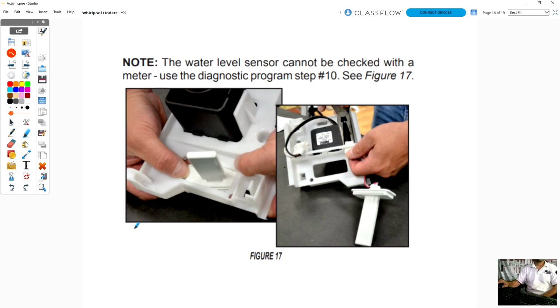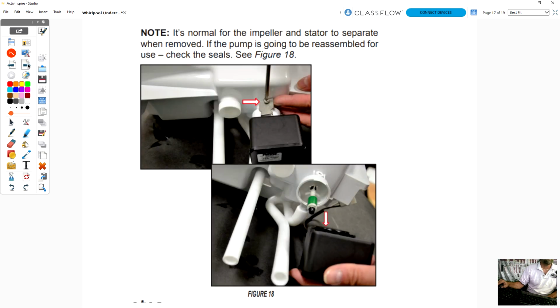So here is our water level sensor. And note what it says here. The water level sensor cannot be checked with an ohm meter or voltmeter. The only way you can tell if this sensor is working correctly or not is you have to go through diagnostics, and step number 10 is the step you need to go into to test that out. So this here is our pump system, but that's the water level sensor.